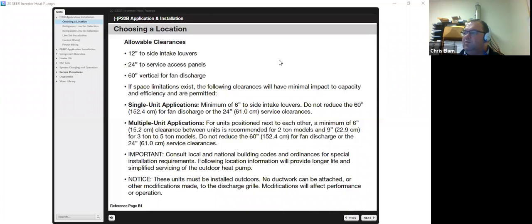If you're doing multiple units positioned next to each other, minimum of 6 inches clearance between the units is recommended for 2-ton models and 9 inches for 3 to 5-ton models. Once again, do not reduce the 60-inch discharge clearance out the top. Notice at the bottom, these units must be installed outdoors. No ductwork can be attached or modifications made to the discharge grill. Modifications will affect performance and operation.